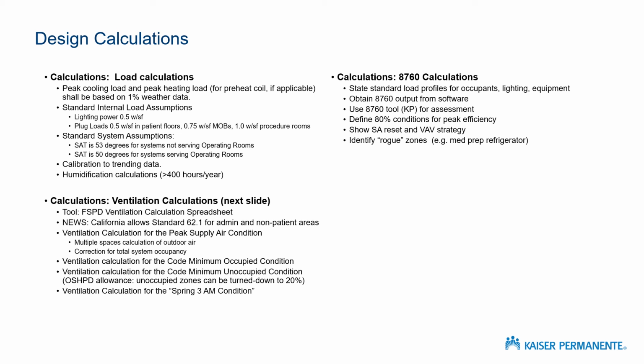And we talked quite a bit in the previous section about the 8760 load calculations. One thing I want to point out here that's kind of specific in hospitals is that we do have rogue zones to deal with in design. A rogue zone is one zone that screws up your strategy. On a patient room floor, the classic example is the med prep room, which has a refrigerator in it, so that generates heat load 24/7. So you may want to reset your air systems to 67 degrees in neutral conditions, but the med prep room needs 55-degree air. So your whole system winds up at 55-degree air. Your energy signature is horrible all year long.